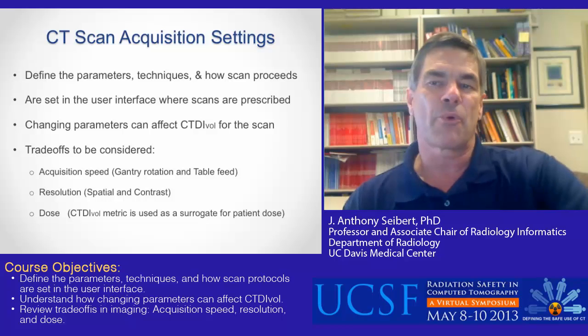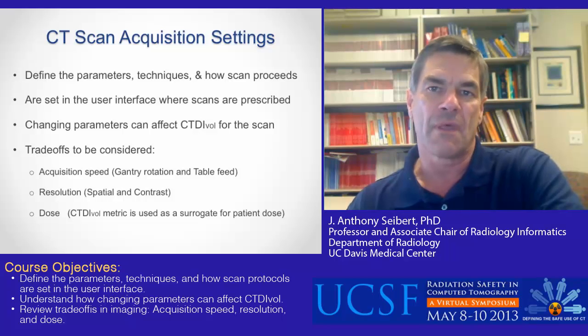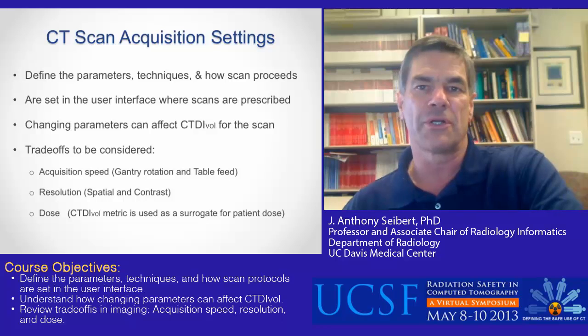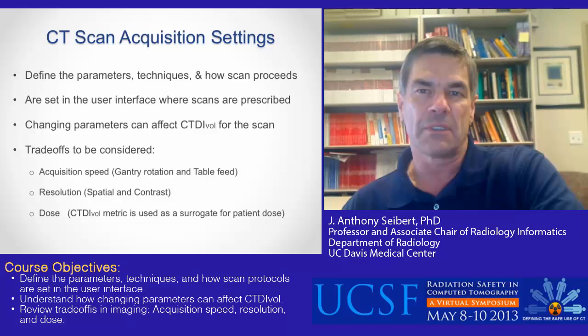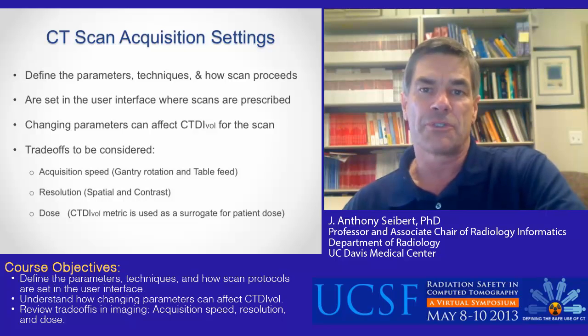CT scan acquisitions define the parameters and techniques to determine how the scan proceeds, and include many post-scan image processing and data presentation instructions. There are many parameters set by the protocol and often adjusted by the technologist regarding patient size or special instructions. Changing any one parameter may or may not change another, and can have an effect on the CTDI vol and dose to the patient. Although CTDI vol is not patient dose, it is used as a surrogate here.